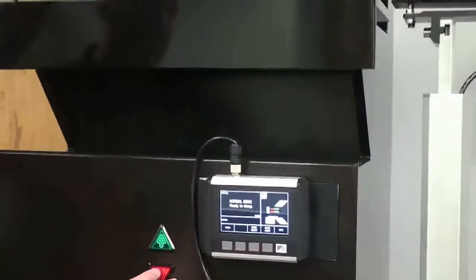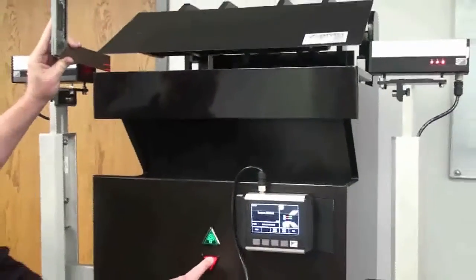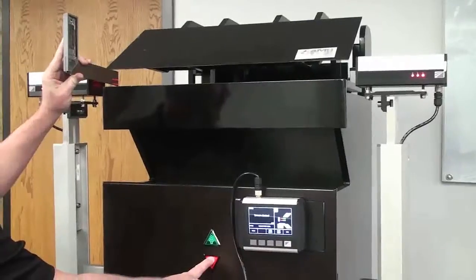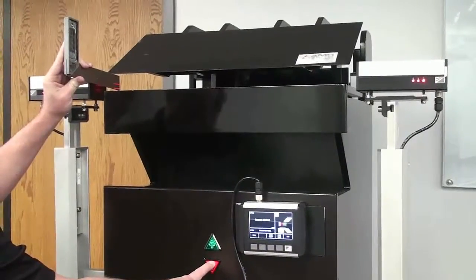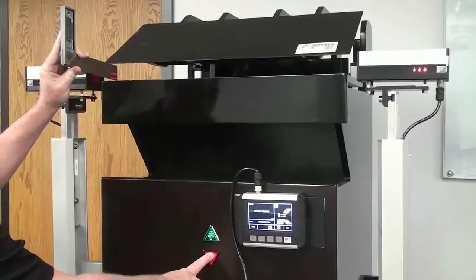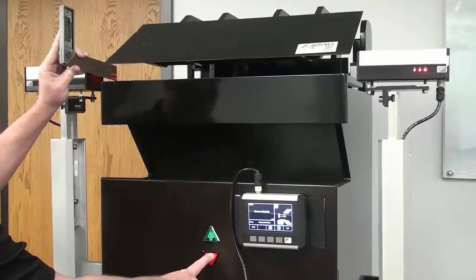And it's in red. So now when I try and lower the clamp, it's still going to let me go down. When I push the foot pedal clamp once, I'm going to get a sensors blocked. This is my indication that you have a blockage. You need to be aware of your surroundings before you push the clamp pedal again.